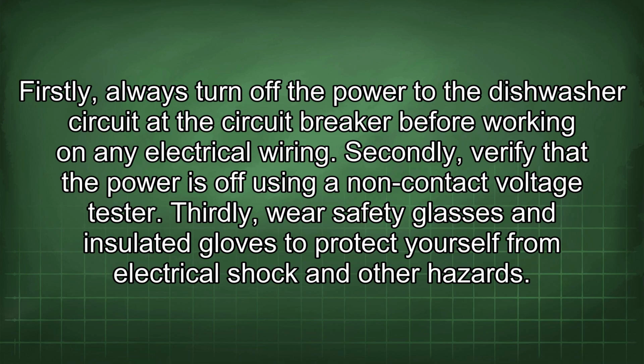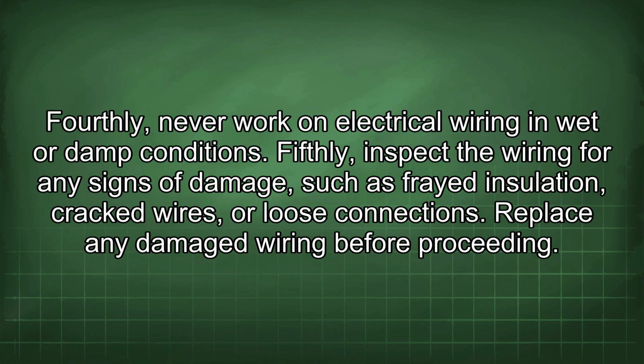Firstly, always turn off the power to the dishwasher circuit at the circuit breaker before working on any electrical wiring. Secondly, verify that the power is off using a non-contact voltage tester. Thirdly, wear safety glasses and insulated gloves to protect yourself from electrical shock and other hazards. Fourthly, never work on electrical wiring in wet or damp conditions. Fifthly, inspect the wiring for any signs of damage, such as frayed insulation, cracked wires, or loose connections. Replace any damaged wiring before proceeding.